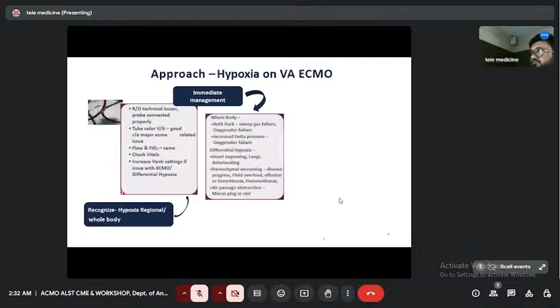Harlequin syndrome. We'll discuss that later. We have to see hypoxia in VA ECMO, whether it is whole body hypoxia or only regional. Whole body hypoxia means both venous drainage and return cannula are affected. That means sweep gas failure or oxygenator failure, or an increase in the delta pressure, that may be because of an oxygenator failure. So differential hypoxia. The most common cause of hypoxia during VA ECMO is differential hypoxia.